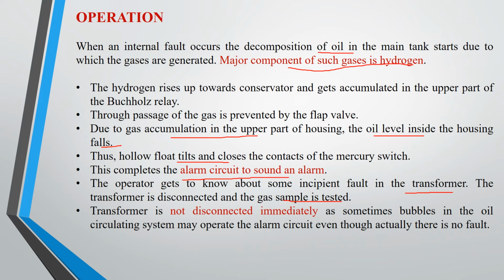Here the transformer is not disconnected immediately after the fault detection, because sometimes the bubbles in the oil may also operate the alarm circuit, although there has been no fault in the system.